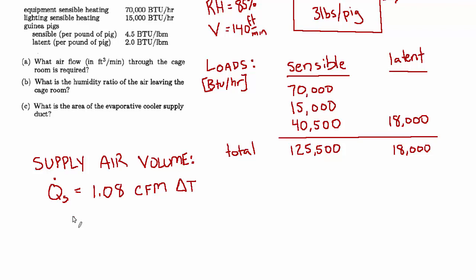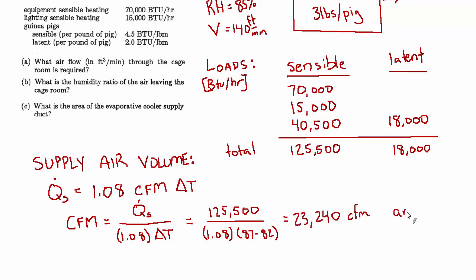Sensible heat load equals 1.08 CFM delta T, and we can rearrange this to solve for CFM. It's going to be the total sensible load divided by 1.08 and the delta T. And substituting in, we have 125,500 divided by 1.08 divided by 87 minus 82, and that gives us 23,240 CFM, which is the answer to A.